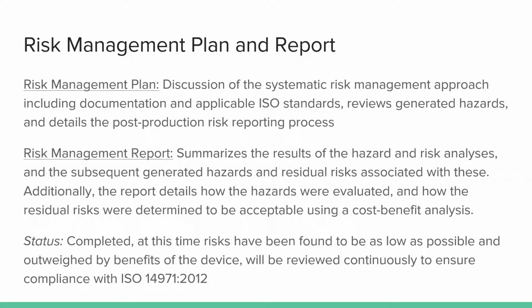The risk management report summarizes the result of our hazard and risk analyses and the subsequent generated risks and residual risks associated with these. It details the residual risks that were evaluated in all of our FMEAs and talks about the cost-benefit analyses. So the status of both of these documents is that they are tentatively completed. At this time, risks have been found to be as low as possible and outweighed by the benefits of the device. We will be reviewing this continually to ensure that the device continues to have compliance to ISO 14971.